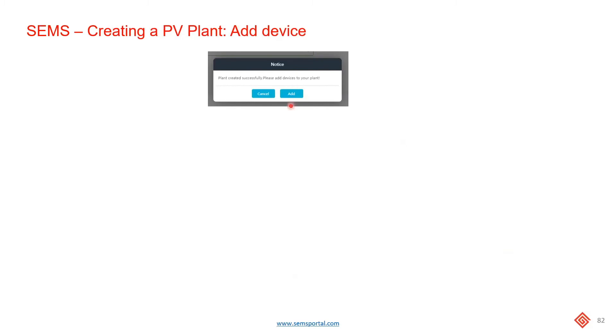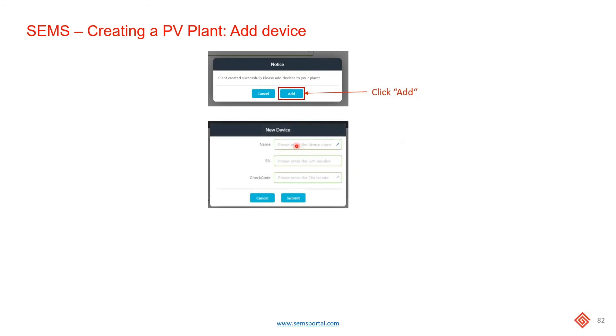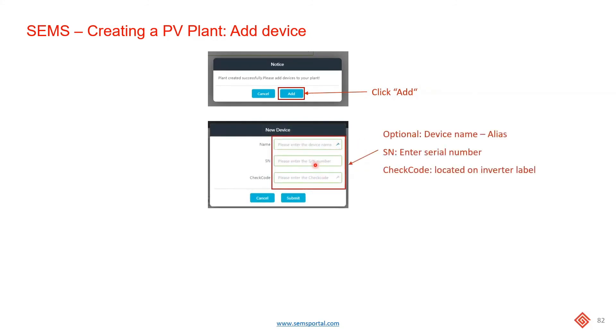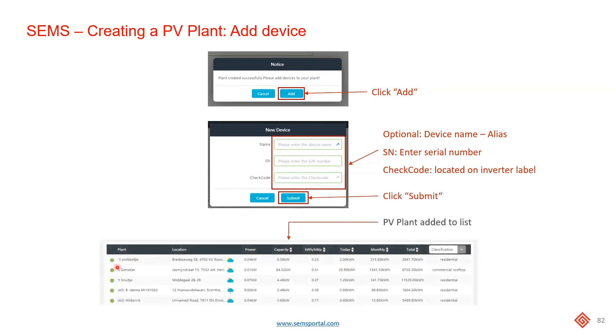Once you've completed that part of the process, the next step is to add the actual inverter. Click on the add button and enter a name for the inverter if you like. What's important is the serial number and the check code. The check code is the six-digit number located on the nameplate on the right-hand side of the inverter. Every serial number has a unique check code, so make sure you've entered the correct check code and then click submit. It will then add it to the list of PV plants under your control.